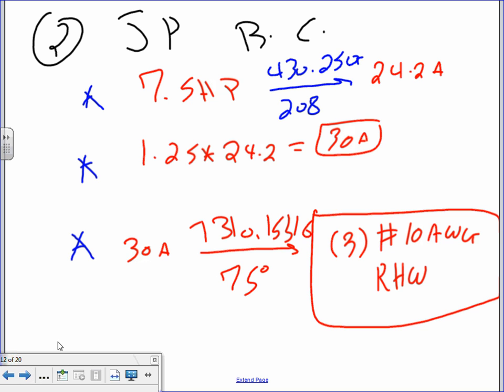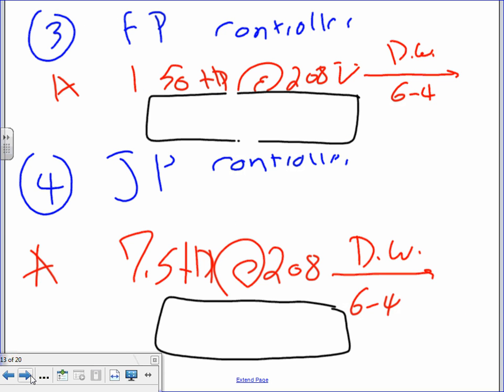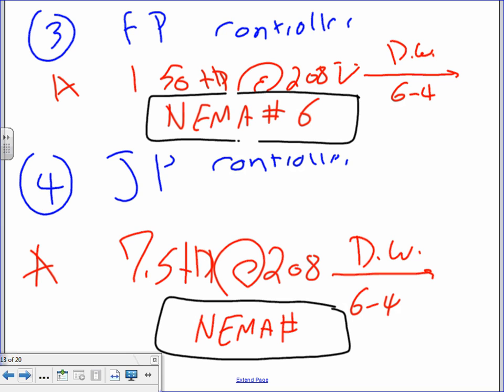Okay, no change. All right, so let's go to number 3. Number 3 is a fire pump controller. Same thing, guys, we've just done it. You take the 150 at 208 volts, Table 430.250 6-4, and that'll get you NEMA number 6. You take the jockey pump to the same table under 208, 7.5 horsepower. That'll get you NEMA number 1. NEMA number 1. Comments, questions, guys? Straightforward, right? That's what it tells you in the sheet. You have the sheet in front of you, and you run it. Run your sheet. Adam, things are good?